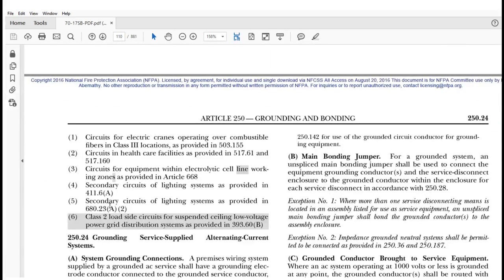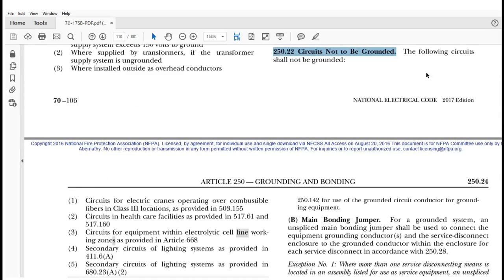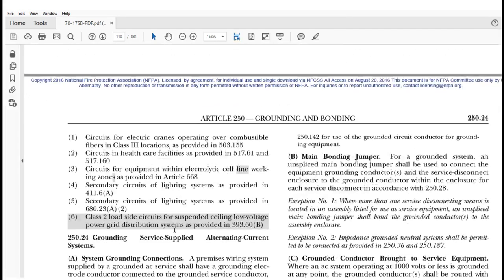So in the 2014 edition, you had 5 items that covered specific areas in the code where the circuits were not to be grounded. They were not intentionally grounded in their installation practice. Well, in 2014, we created this new article, 393. This new article dealt with ceiling power distribution systems that were low voltage design, and that got a lot of prominence in 2014 as one of the new articles. But the nature of those are Class 2 circuits on the secondary side of a transformer that creates this Class 2 low voltage system and this low voltage grid distribution system, which can be used for a multitude of things, whether it's office areas, to power computers, whatever it's needed where it didn't need to be connected to a grounded conductor application.